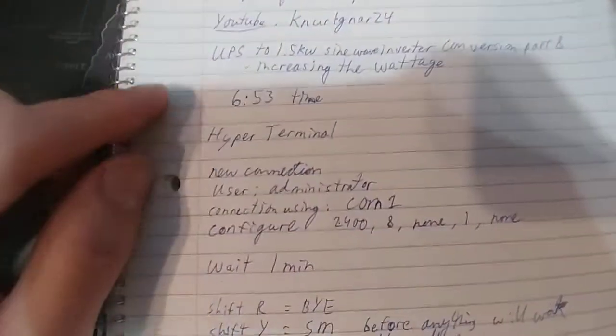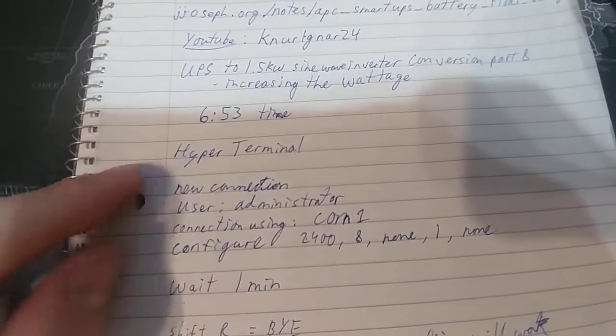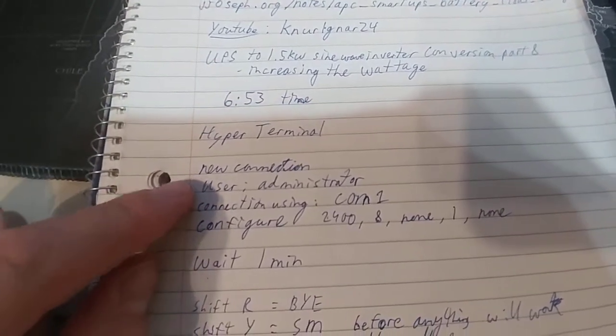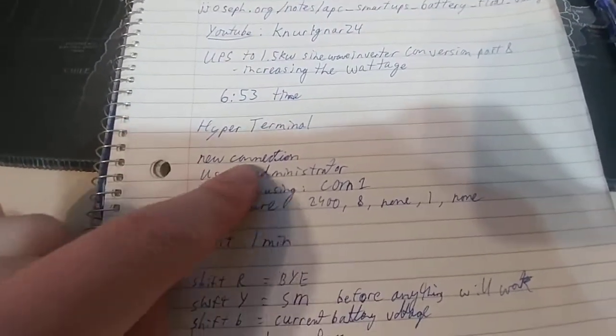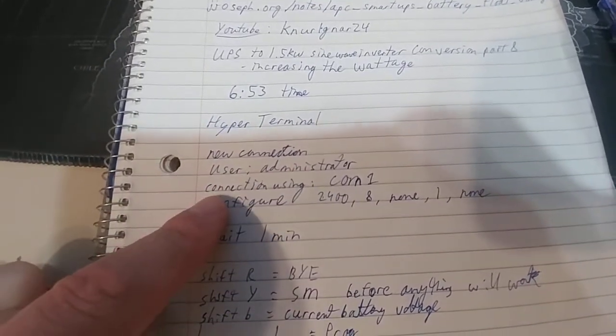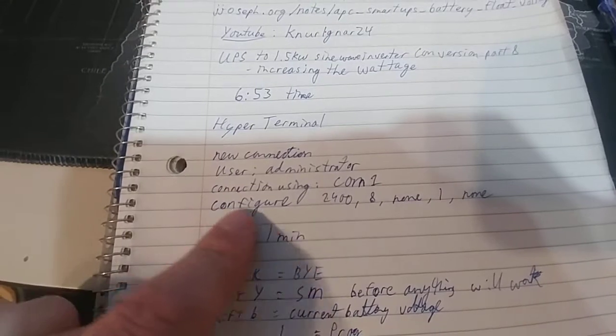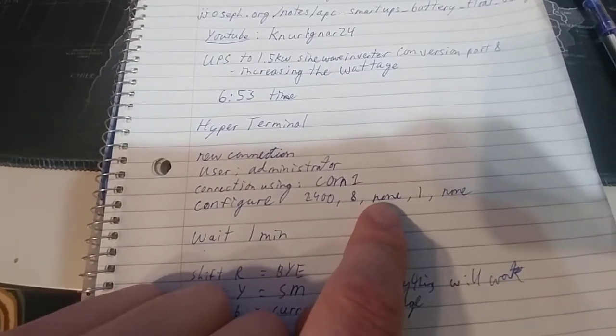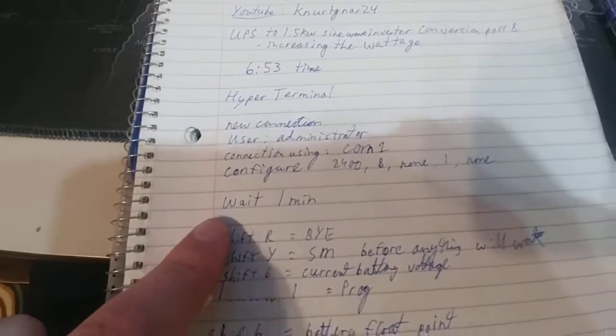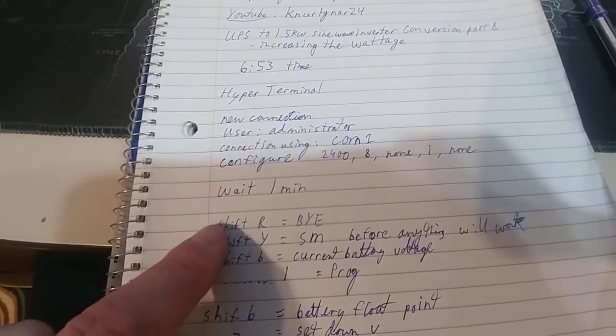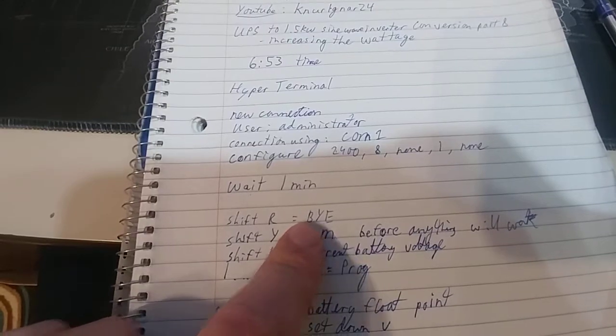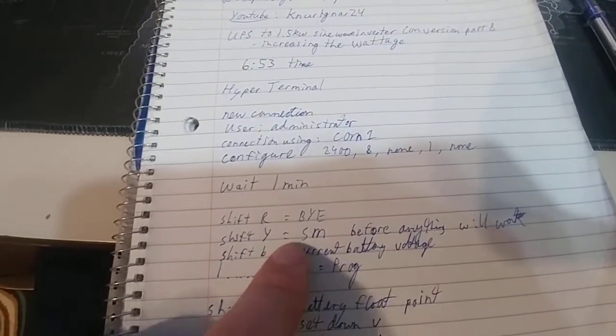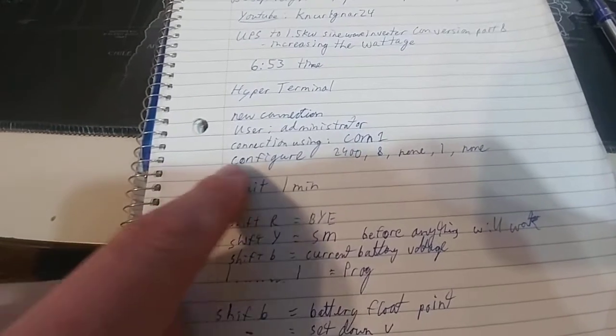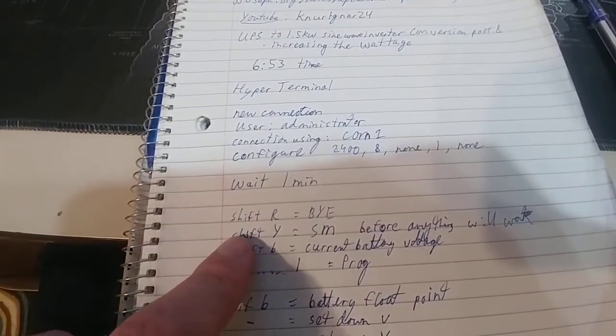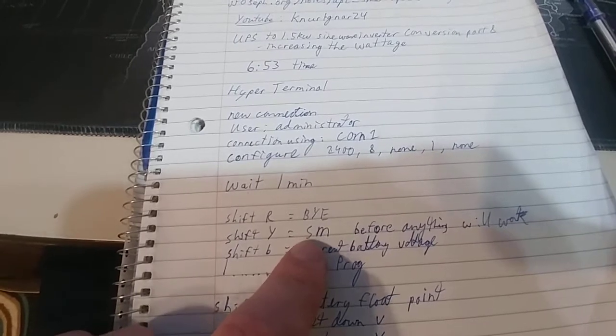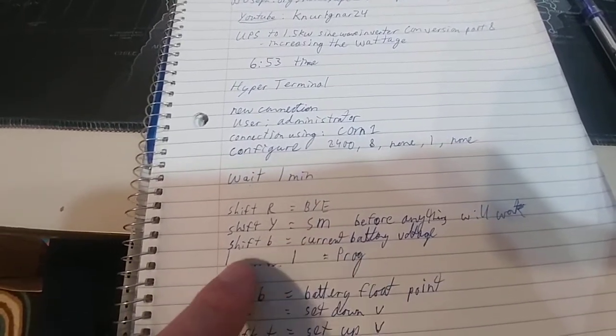Okay, so you need Hyperterminal. That's an absolute must. And you'll do new, we're going to go through this quickly, but basically new connection. I call it administrator, you can name it anything. Connect using COM1. Configure it to be 2400, 8, none, 1, none. So wait about a minute. Shift R turns it off. Shift Y turns it on. After you've connected and configured and it says connection, you have to press Shift Y and it'll say SM. That means it's ready to go.